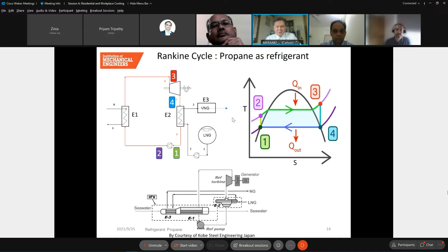A gas turbine is generally rated at a temperature of 15 degrees centigrade. However, when the air temperature goes up, efficiency goes down. In case of Japan or India, in summertime when the temperature is quite high, the performance of the compressor will drop from 100% down to 82% if the ambient temperature is 40 degrees centigrade.